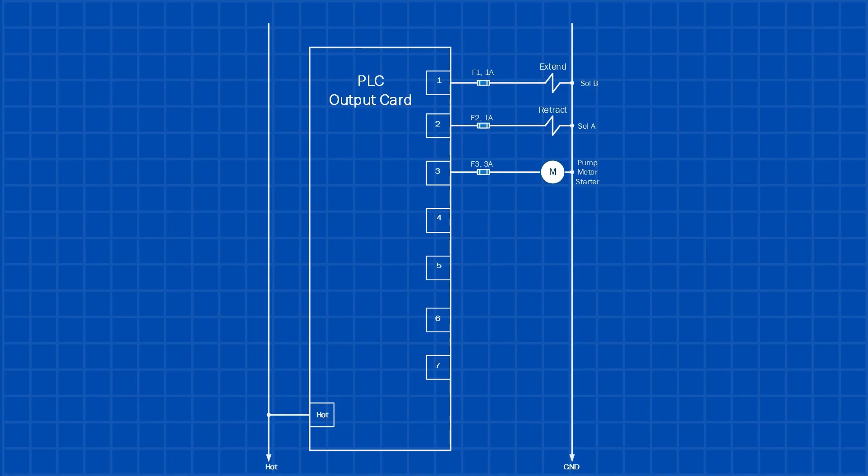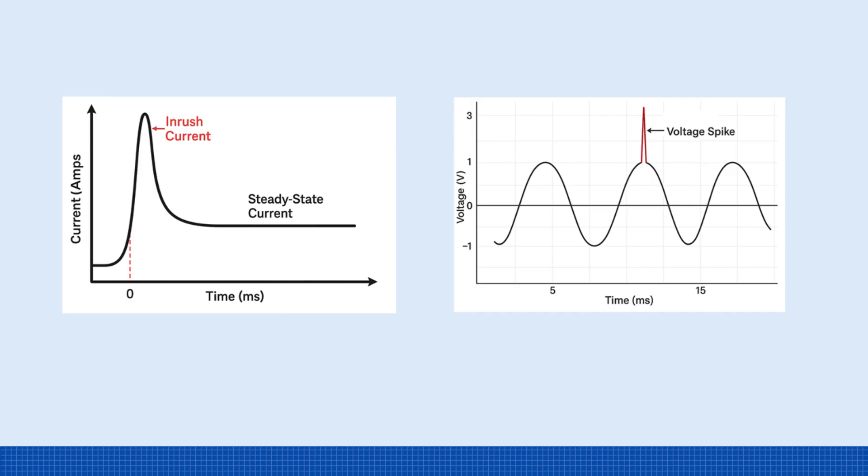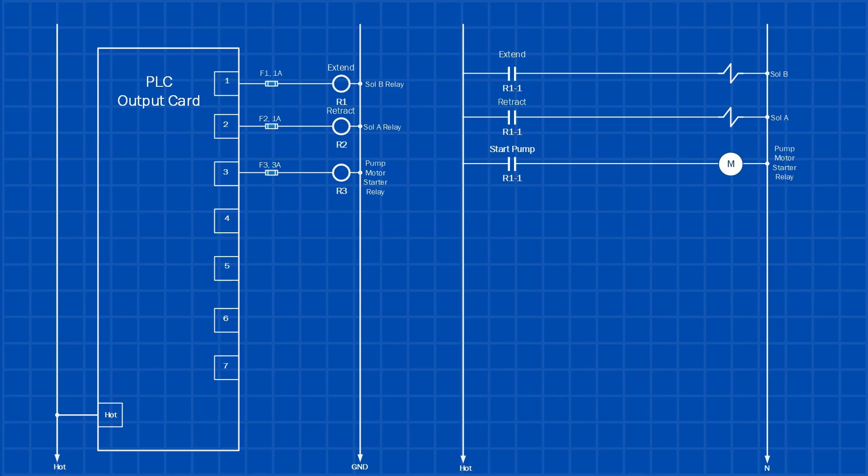There are three main reasons to use a relay. The first one is isolation. Here I'm showing a PLC output directly connected to solenoids and a motor starter, which we'll explain in more detail later. Most PLC output cards use transistors and other electronic components. However, some cards come with built-in relay outputs. In cases where the output card doesn't have relays, directly connecting inductive loads like solenoids or motor starters is not a good practice. That's because inductive loads generate inrush currents and voltage spikes when they turn on or off. These spikes can damage the sensitive components inside the output card. To prevent this, it's good practice to use an external relay with low coil current. The PLC simply energizes the relay coil, and the relay's contacts are used to safely switch the solenoids or motor starter.